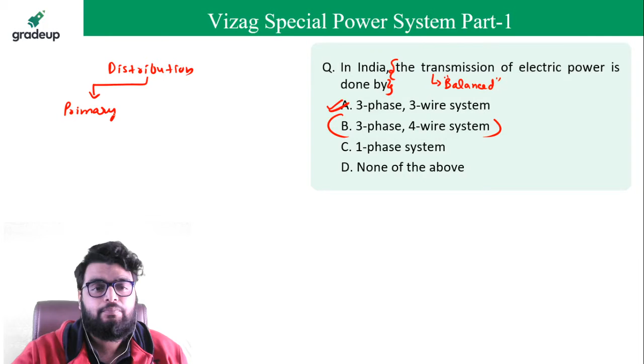See, the three-phase, four-wire system is basically used in the primary distribution, in which you require a voltage level of 66 to 33 kV. And why do we use the four-wire system? The fourth wire or neutral wire is used because a primary distribution contains loads, for example factories and mining industries. These types of loads create unbalance in the system. That's why a fourth wire, or neutral wire, is required in this type of system.